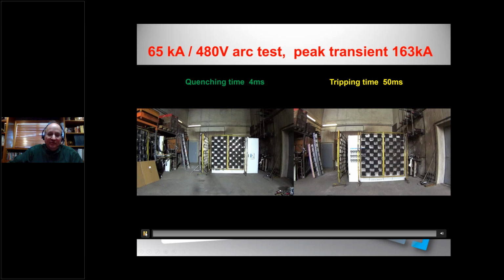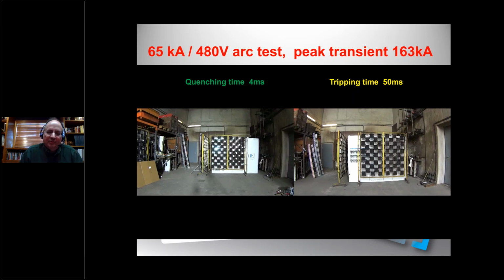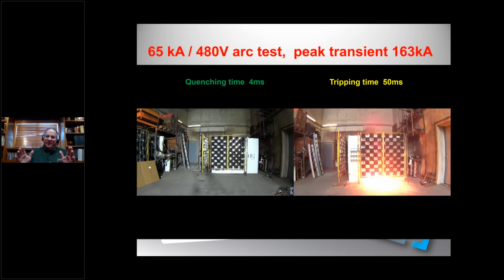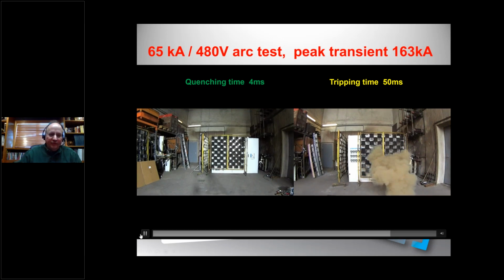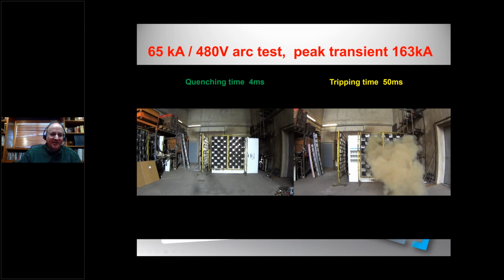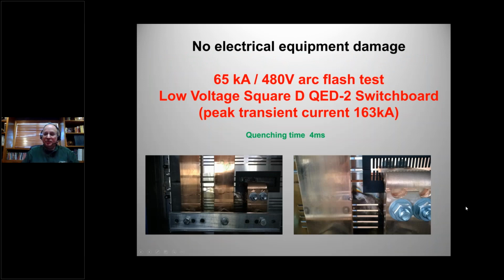So I'm beginning the video now. If you look very carefully at the switchboard on the left, you should see a brief flash of light right there. And on the right, at the 50 millisecond mark, you have no problem seeing what occurs to the switchboard on the right. So both of these switchboards pass type testing, to be clear. But the switchboard on the left with the arc quencher, this is what the bus looked like. There's a little bit of scoring.